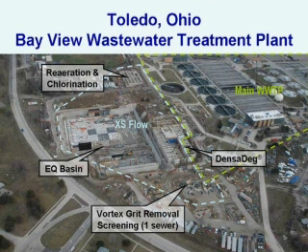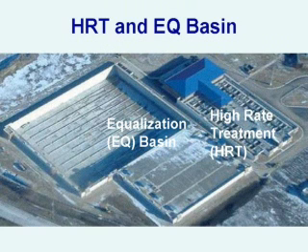There is somewhat less consistent performance due to the variability of the ballast media, but again, in the case of Toledo with the subsequent equalization or secondary treatment, that was not as much of a concern. The city did select Densadeg, and as was mentioned at the beginning of this webcast, we're not here to promote any particular technology. I think the take-home message is that each case needs to be looked at individually to see how these considerations impact the particular site.